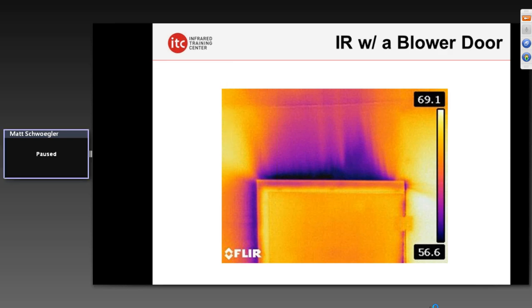Infrared is often utilized in building systems along with what's called a blower door — basically a pressurization fan where you can depressurize or pressurize a building to help diagnose air leakage-related issues. In this case, around the knee wall attic access hatch in a residential home, the air leakage is showing up very apparently thermally — along the top we're seeing the effects of cold air coming in, something that would not reveal itself if we were not using that blower door.